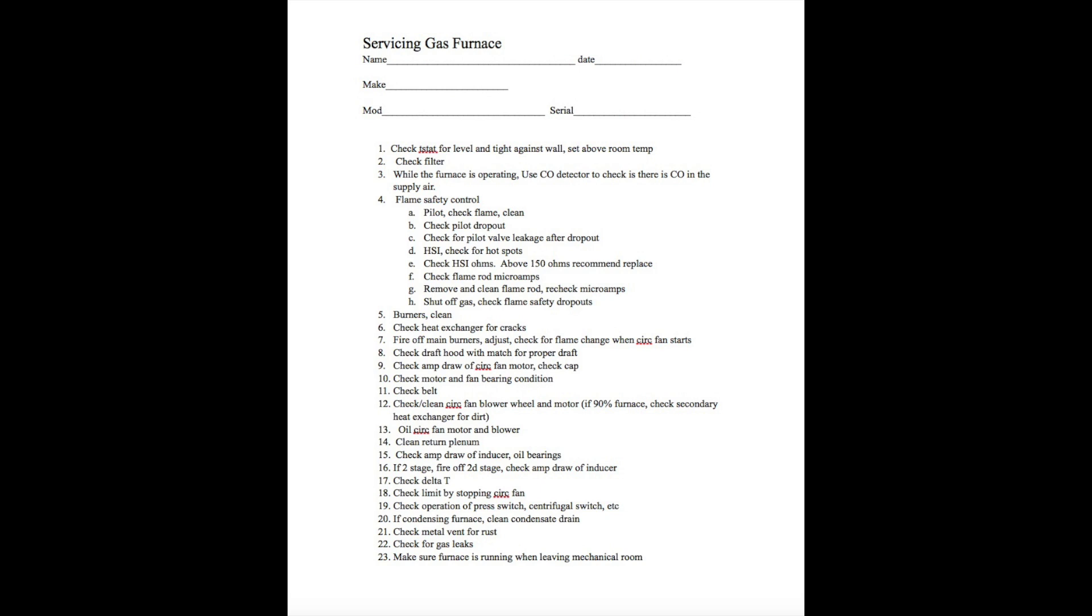The next thing we're going to do is go to the flame safety control. If this is a pilot operated furnace, it has a standing pilot. You're going to check the pilot flame. You're going to be looking to see, is it yellow or is it blue? It should be blue, it should be kind of roughly looking, it shouldn't be lazy like a candle flame. And clean the pilot. You can clean them, oftentimes with a little bit of compressed air. Sometimes you have to take them apart. But you need to get any crap that's in there out, because sometimes they'll get plugged up and that will cause that lazy flame.